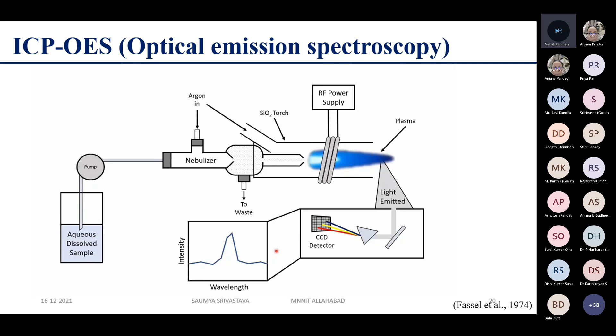To generate the plasma, first argon gas is supplied to the torch coil and high frequency electric current is applied to the work coil at the tip of the torch tube. Using the electromagnetic field created in the torch tube by the high frequency current, argon gas is ionized and plasma is generated. This plasma has high electron density and temperature, and this energy is used in the excitation or emission of the sample, and the solution samples are introduced into the plasma in an atomized state through the narrow tube in the center of the torch tube.